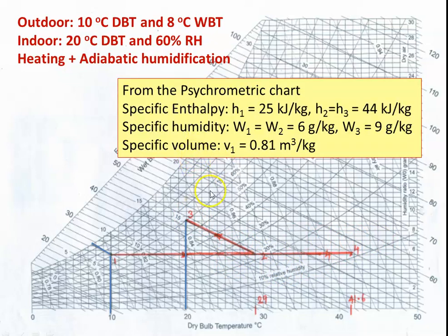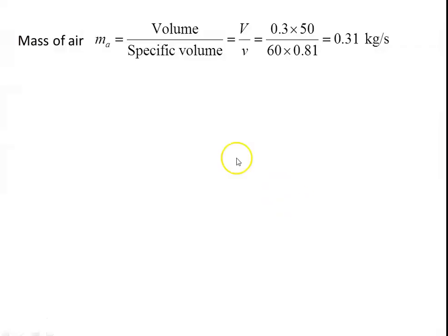From the psychrometric chart, read: H1 = 25 kJ/kg, H2 = H3 = 44 kJ/kg. Specific humidity: W1 = W2 = 6 g/kg, W3 = 9 g/kg. Specific volume at point 1 is 0.81 m³/kg. Calculate mass of air: M = volume / specific volume = (0.3 × 50) / 60 / 0.81 = 0.31 kg/s.